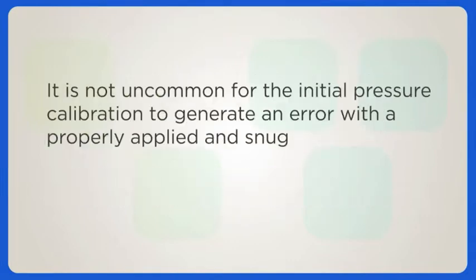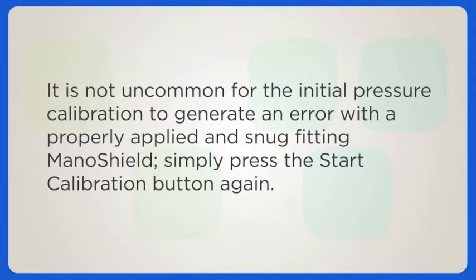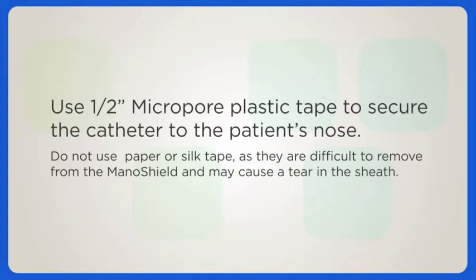It is not uncommon for the initial pressure calibration to generate an error with a properly applied and snug fitting ManoShield. If you do receive an error message, simply press the start calibration button again to recalibrate. Use half-inch micropore plastic tape to secure the catheter to the patient's nose. Do not use paper or silk tape, as these are difficult to remove from the ManoShield and may cause a tear in the sheath.